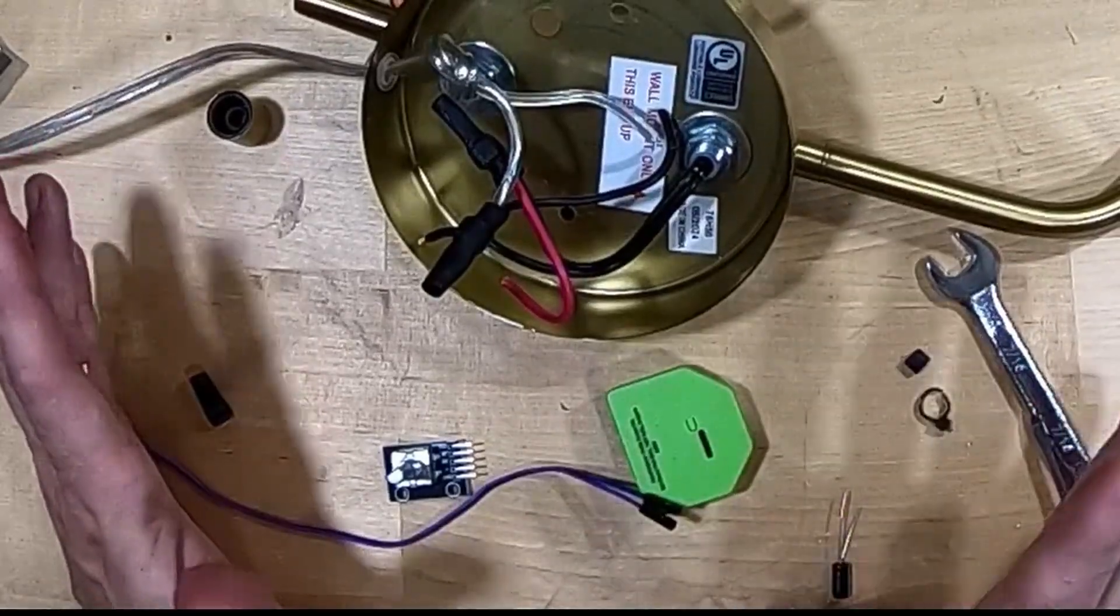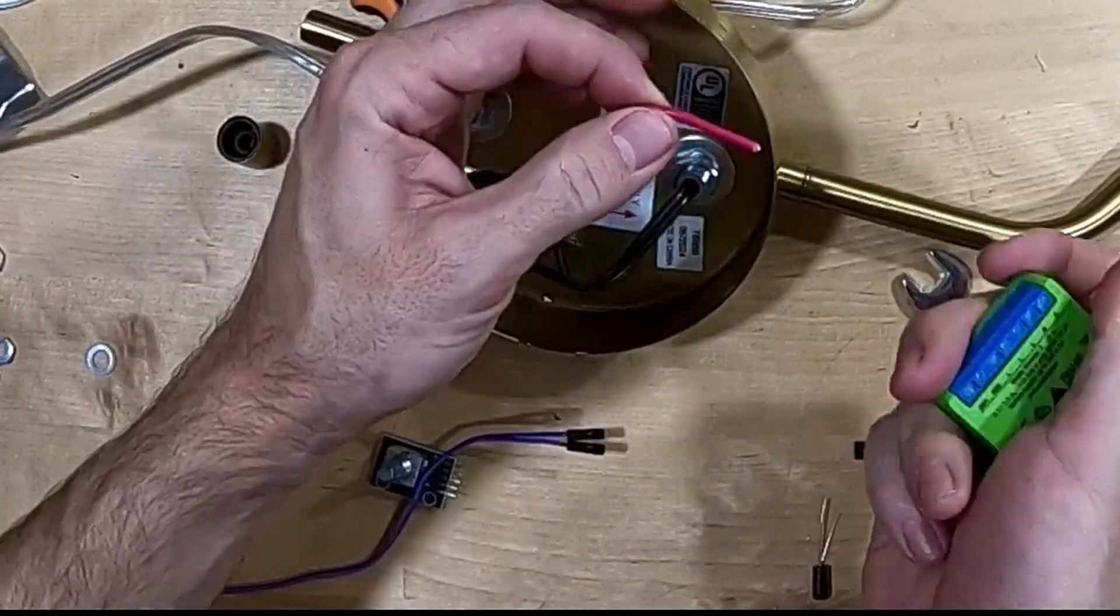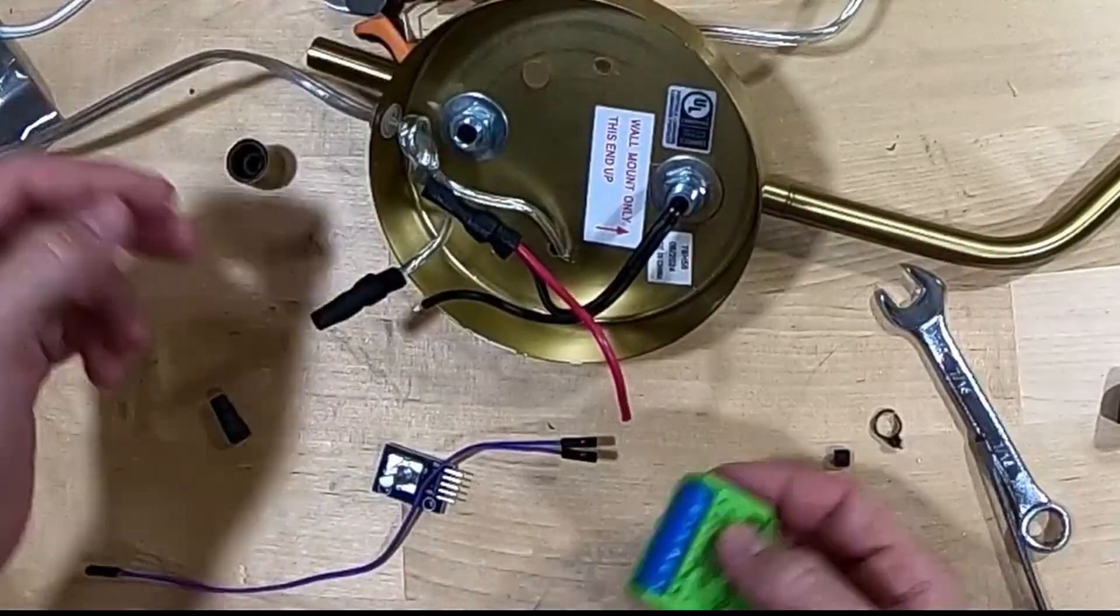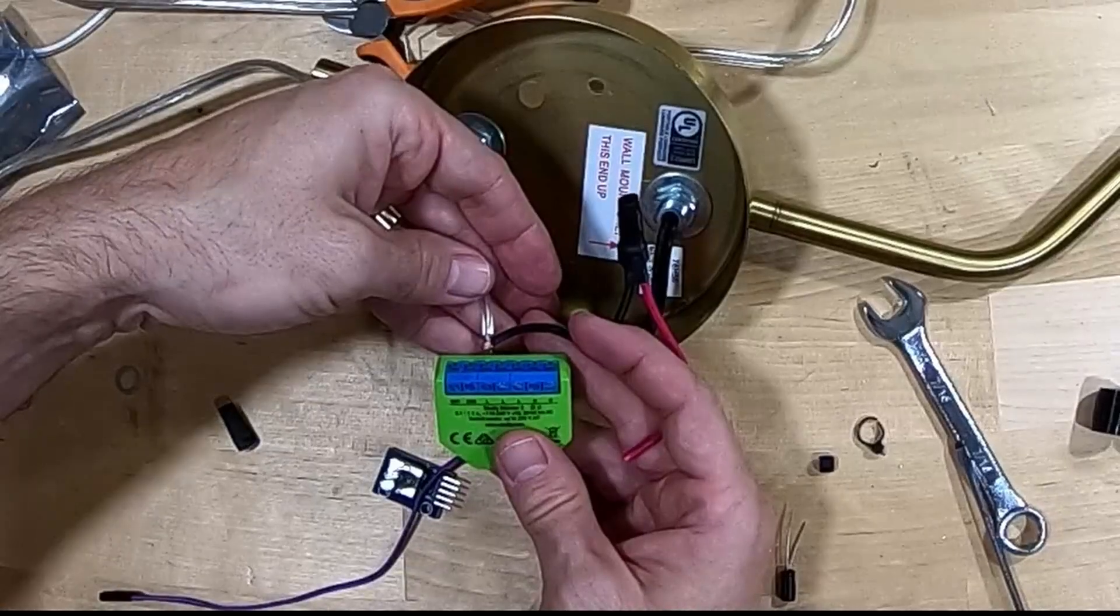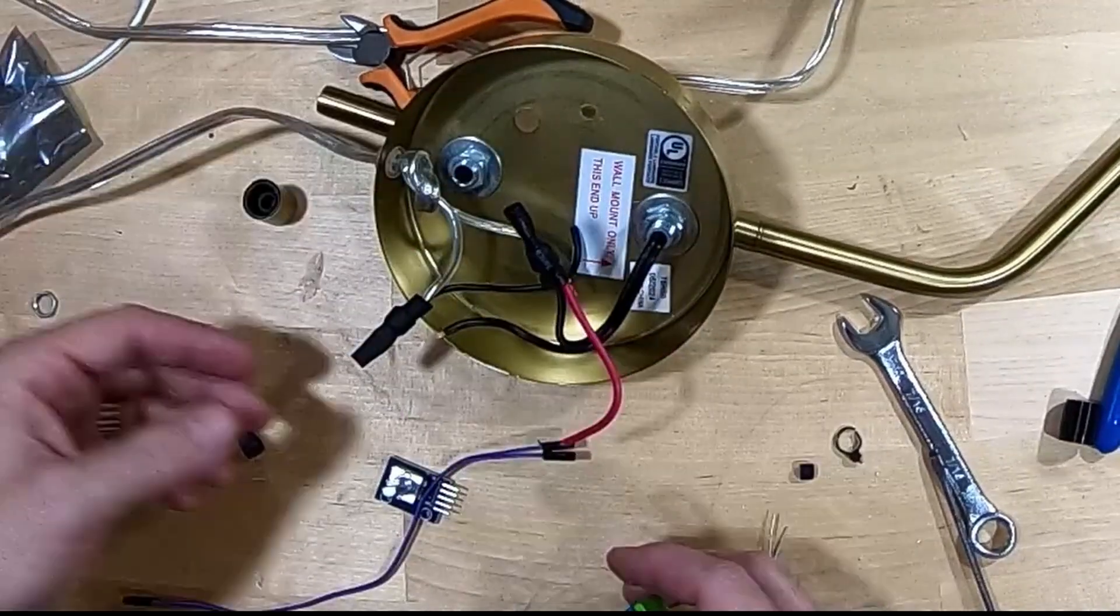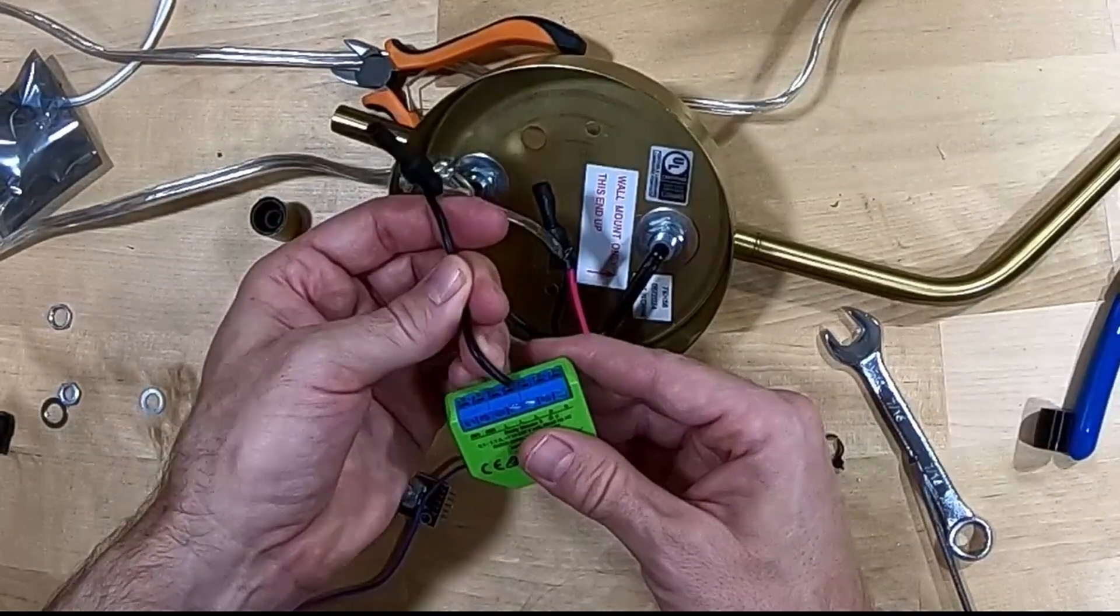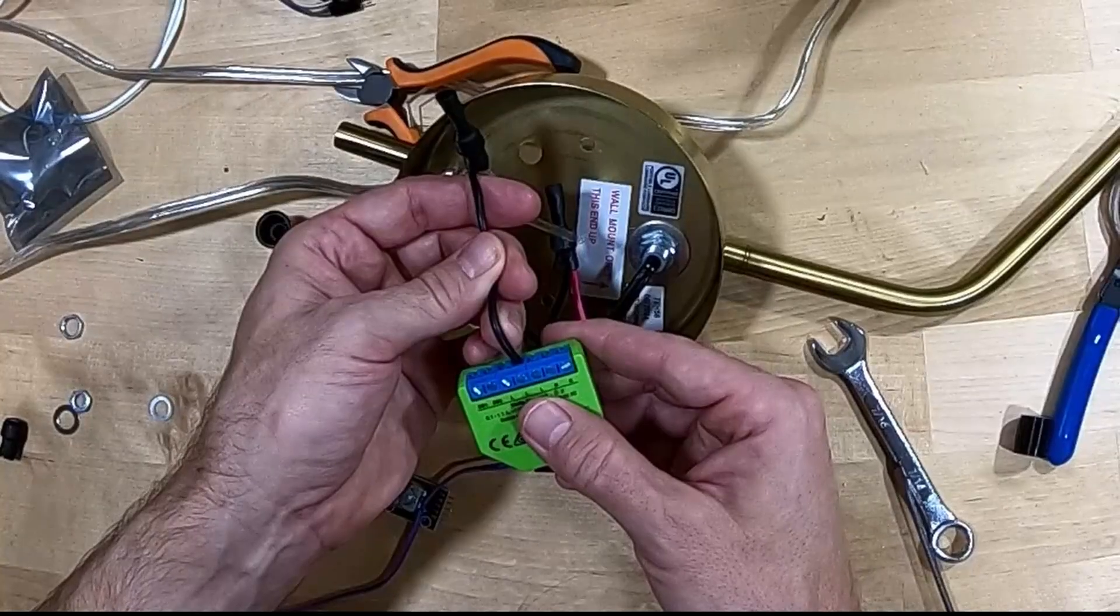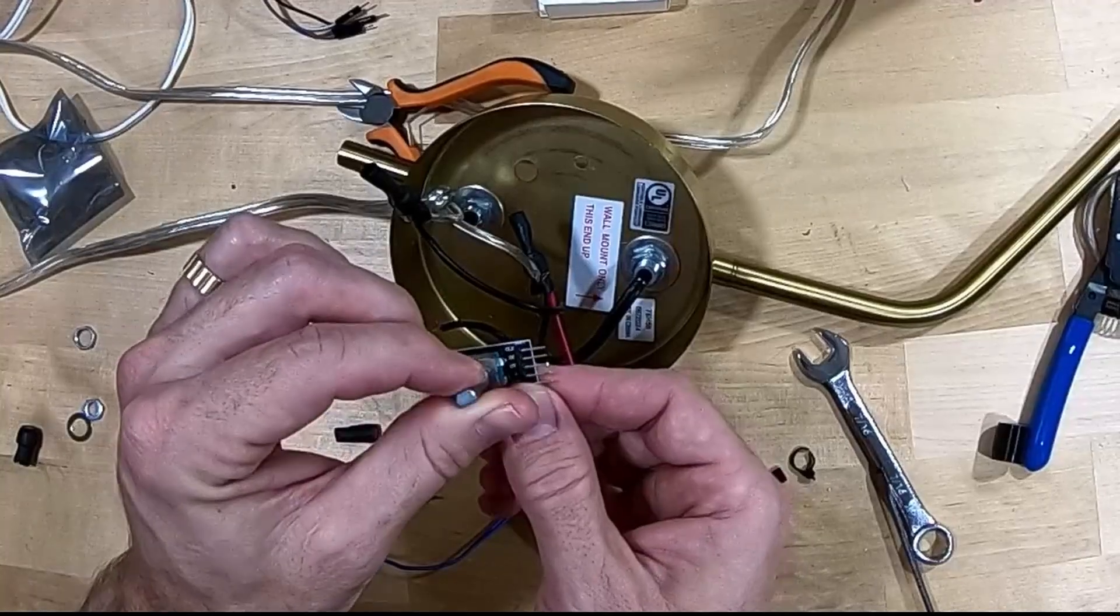All right. So how is this going to be wired? So the wire going to the bulb itself, the hot wire is going to go into O. The neutral is going to go into neutral, but of course you want the neutral for the bulb in parallel. So that goes into N here. The load going into the sconce. Well, I think it could go into any one of these, but I just always choose the middle one. But I think they're all wired into parallel.